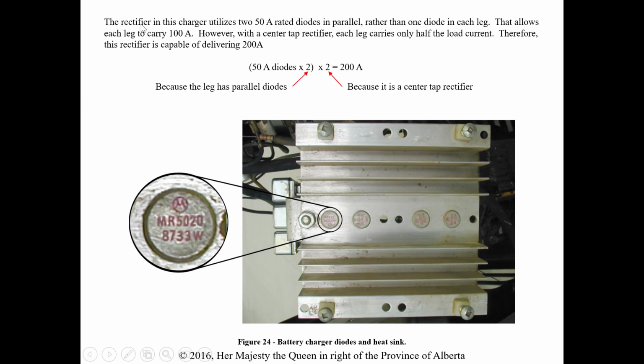So to look at the actual design in this rectifier, this charger uses two 50 amp rated diodes in parallel rather than one diode in each leg. That allows each leg to carry 100 amps. Okay, so 100 amps because of the parallel connection. However, with a center tap rectifier, each leg carries only half the current. Okay, and that's like what we talked about before for rectification. If a diode's only on for one alternation out of two in a full cycle, it only has current going through it half of the time. So on average, it's basically rated for half the current.